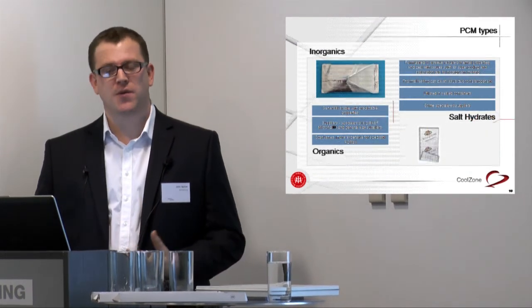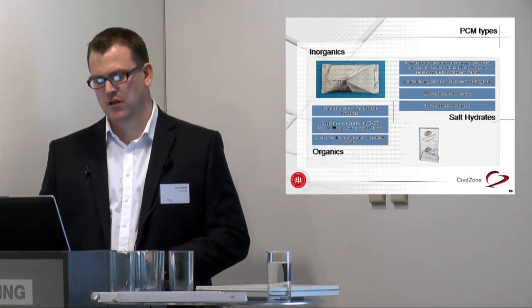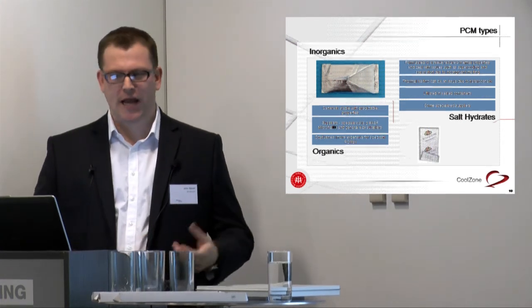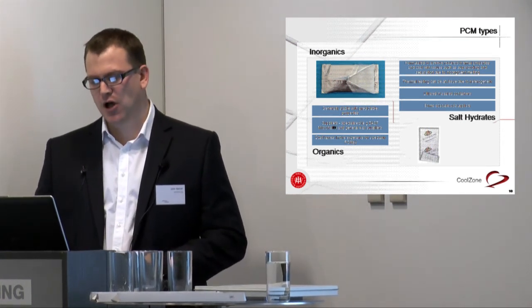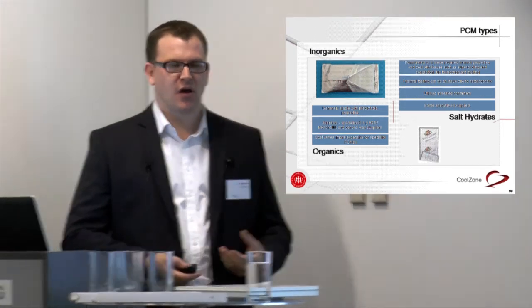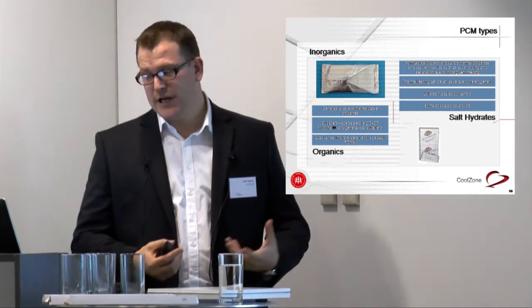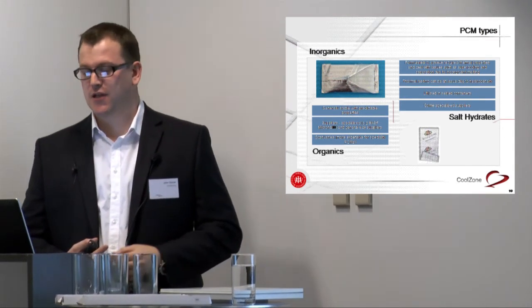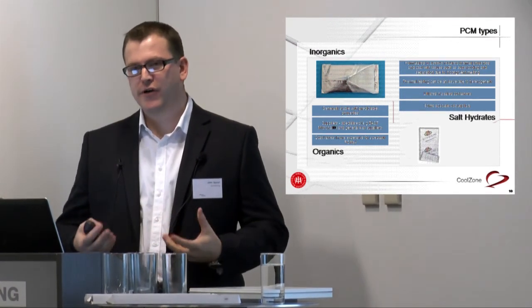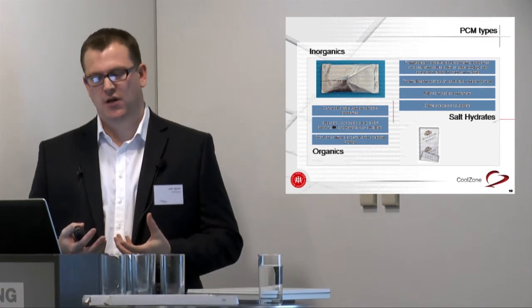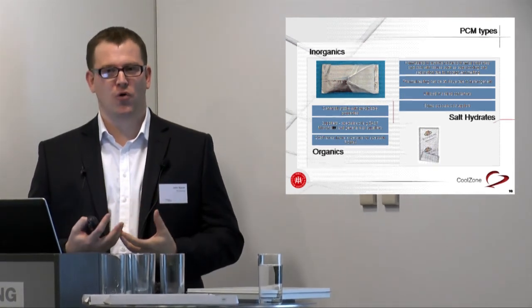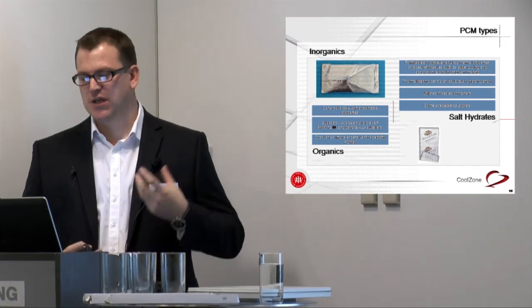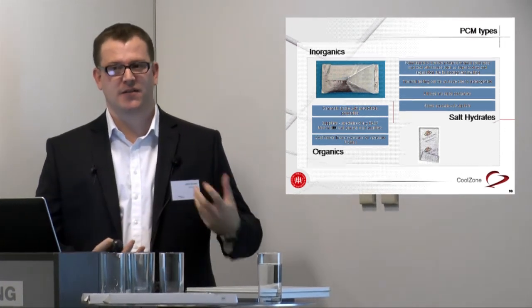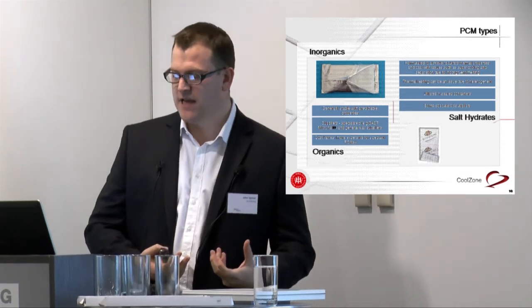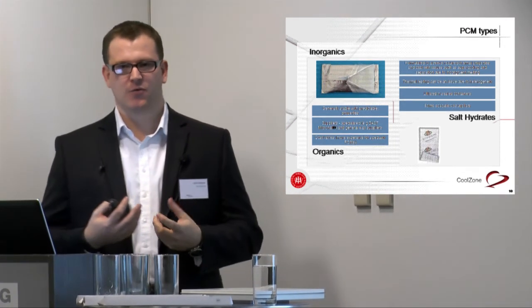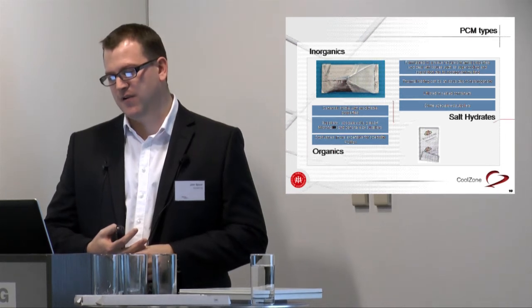Now there are a number of different types of phase change materials. There are inorganics and organics, and salt hydrates. Organics are naturally occurring. They might be things like palm oils, so they have very good thermal storage, but the main problem is they have very poor fire properties. So if you put that in the ceiling, we can't guarantee that we're going to pass a fire reaction test every time. They're erratic when it comes to fire properties.